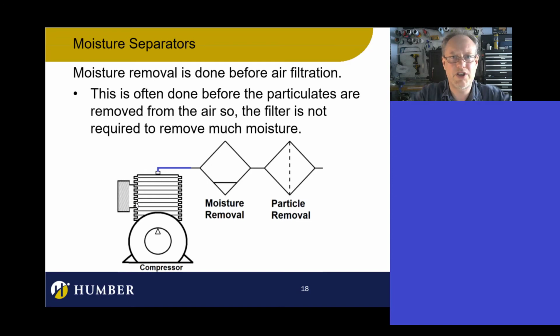So what's going on here is that it's important to note that when we are putting a moisture separator specifically into our pneumatic system, we put that moisture separator right after the compressor. Because if there's a lot of moisture coming out of your compressor and you put it through a filter, that's cool, but the filter will remove some of that water. But that's stressing your filter to some degree, or sorry, your strainer.